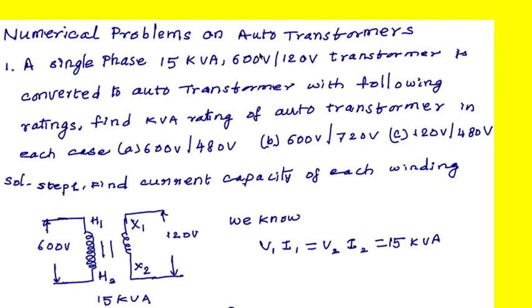Let me draw the two-winding transformer parameters. This is a step-down transformer — 600 volts primary, 120 volts secondary. Let me assign high voltage winding terminals as H1, H2, and the LV winding represented with X1 and X2. For a transformer, the kVA rating whether measured at primary or secondary side remains the same: V1·I1 = V2·I2 = 15 kVA. The primary voltage is 600 volts and secondary voltage is 120 volts.